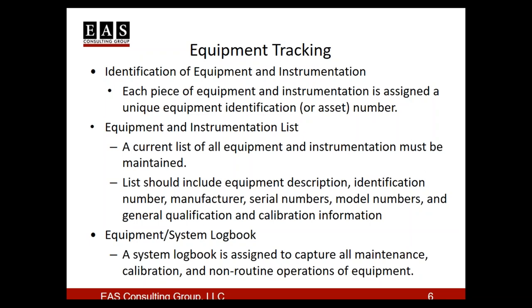The list will include a description of the equipment, that identification number, and numbers that are applicable to the equipment that's there. For each type of equipment or each piece of equipment, there will also be an equipment or system logbook. This is used to capture all the maintenance and calibration activities, as well as any non-routine operations of the equipment.